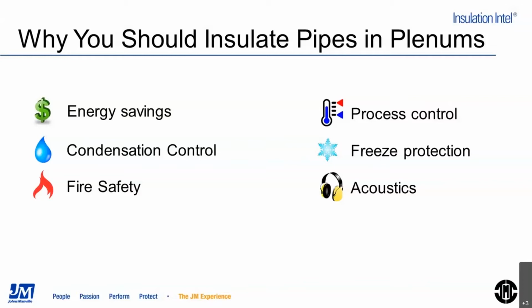For cold or other fluids, you really need to be protecting them also from frost, from cold temperatures. While the plenum space has the air movement with the occupiable and conditioned space, it's not fully conditioned, so you can have extreme temperatures in this environment. We want to also insulate pipes because certain types of insulation will provide the fire safety, so that will protect the combustibles from reaching high temperatures. So that's the fire safety benefit. And certain types of insulation provide acoustics benefits. So with the plenum spaces, oftentimes above occupiable spaces or offices, some of the pipes could be for rainwater, and as the rain is happening and you have the rain rushing through the pipes, the occupants of the space do not want to hear that. So that's another huge benefit of the insulation.